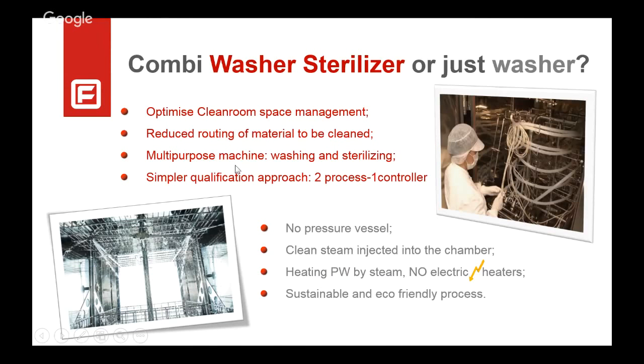And the multipurpose machine is very interesting also as far as concerns the qualification, because you have only one machine, one controller, but two processes. So the validation time of the overall machine will be reduced by about 30%, because many of the controlling systems, for instance, to make a very simple example, password handling, are the same because we have only one machine. So it doesn't matter if we are running a washing cycle or a sterilization cycle.